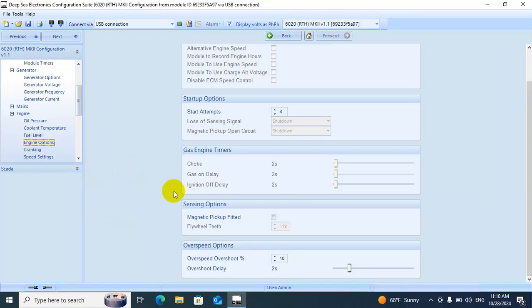And also this setting is for when the MPU is fitted to the generator, or alternator housing. We have to tick this one, and also add the number of teeth. Otherwise, if we are not using MPU, we have to keep it like this. It will read the RPM from the AC or the frequency.